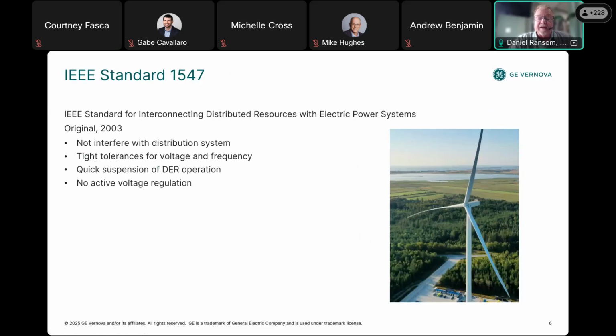So if we look back in time, let's start with IEEE Standard 1547, the standard for interconnecting distributed resources with electric power systems. It's evolved over the years since its introduction in 2003. The 2003 standard emphasized that DERs not interfere with distribution system normal operation. In addition, the other priorities of this original standard were worker safety and public safety. Tolerances for voltage and frequency excursions were very tight, and the standard mandated quick DER operation suspension. It mandated that DERs shall not actively regulate voltage.